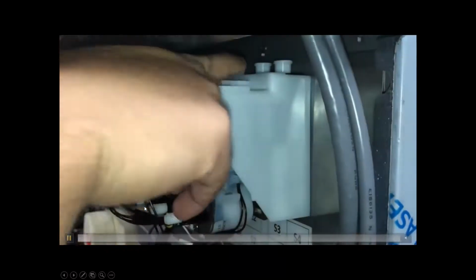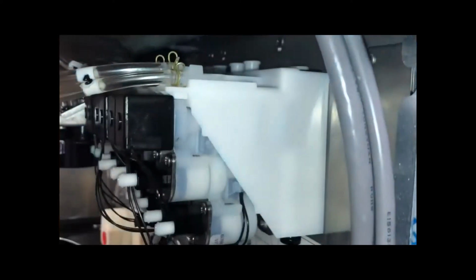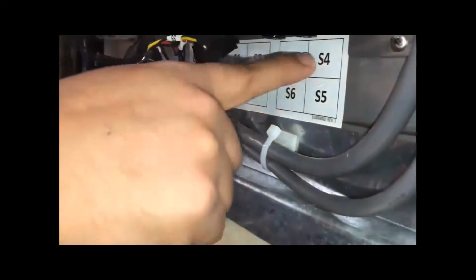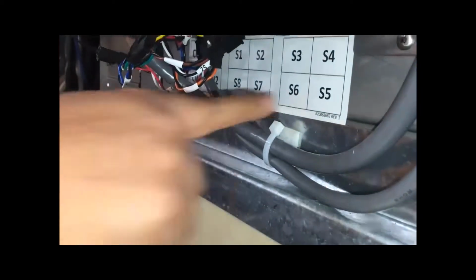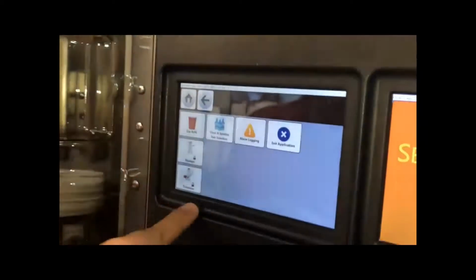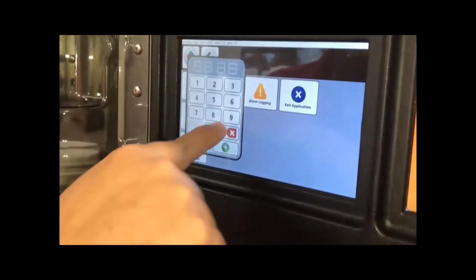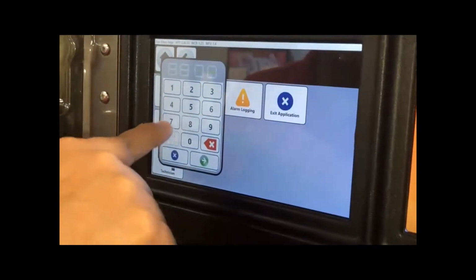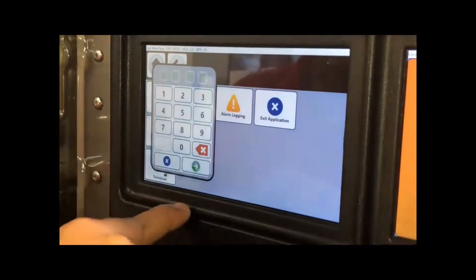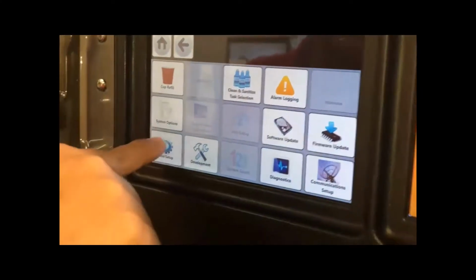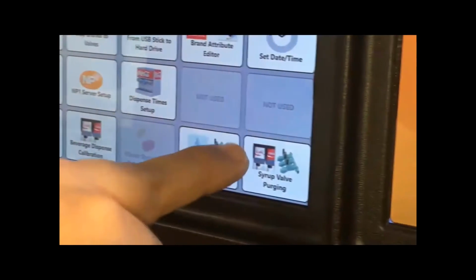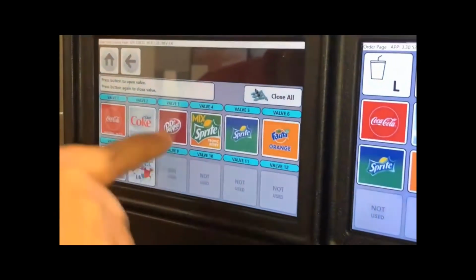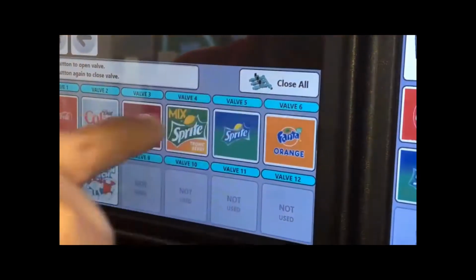Here's a quick video. So those are our shutoffs right there, you want to push those down to shut off your pressure, and depressurize your system. For example, this circuit here is 3, 4, 5, and 6. We're going to go back into our technician unit setup, syrup valve purging, and depressurize 3, 4, 5, and 6.